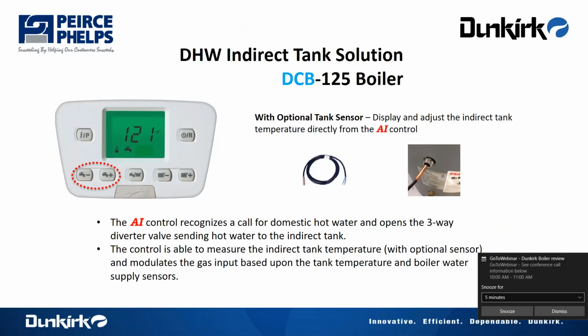When we're using an indirect water heater with the DCB 125 boiler, a simple sensor kit is purchased. The sensor rides in the dry well of the indirect tank and then just plugs into the terminal strip on the boiler, and then the boiler is going to operate as if it's a combi with the diverter valve rolling. This shows the bottom of the combi boiler. Letter I and letter C are system supply and system return. Letter G and letter D on the combi are domestic hot water supply and cold water inlet.